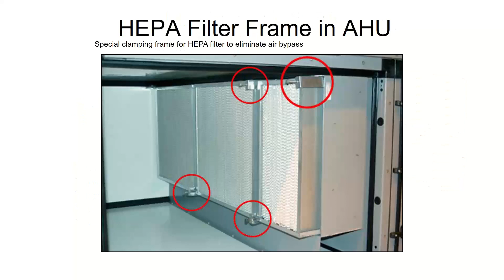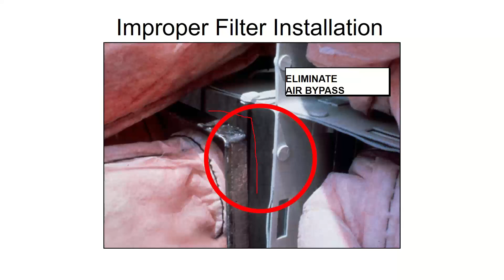Just to give you an idea, this is bag filters. If there's a gap, air is going to take the path of least resistance. Why would it go through the bag when it can go through the gap? So I need to get rid of the gaps, and with cartridges and HEPAs I'll even caulk the gaps up. The more important the project, the more time I'll spend getting these filters in correctly. If it's just some insignificant, normal office building, I'm not caulking all the filters. But if it's a surgical suite, I'm absolutely caulking all the filters, and I'll have multiple filters: pre-filters, then the regular filter, then a post-filter. I'll have tons of filtration there.